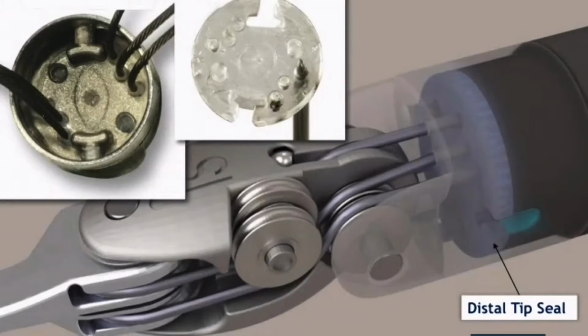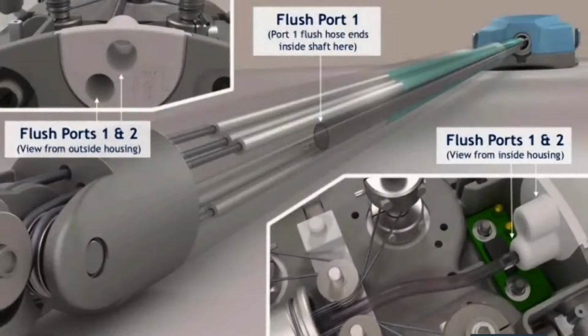I think you can have a better appreciation of this as we remove the distal cap and get inside the actual SSI instrument. This is the blue instrument, right? If you look in the upper left corner of your screen, you have two flush ports, port 1 and port 2. Port 1 is at the upper part, actually the bottom, and there is a tube from this connection that goes down the shaft. And if you look in the middle of the slide, you see flush port 1, where the cleaning fluid enters and flushes, and then it reverses back out into the housing, where, down in the bottom right-hand screen, you can see where the other port would flush and cause all the bioburden that's been backed up from the shaft into the housing to be flushed out there.